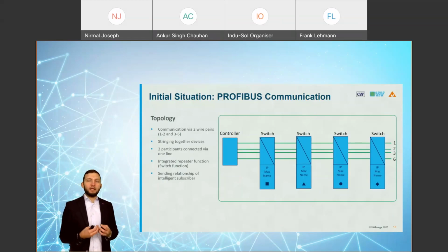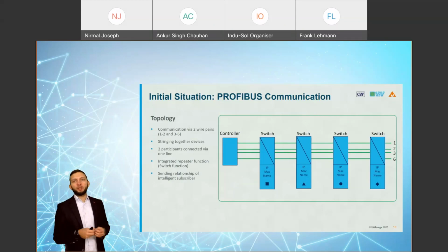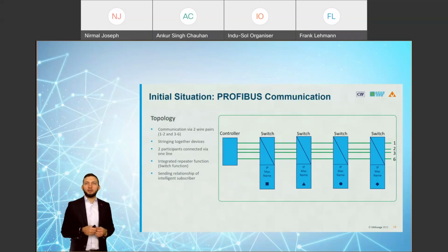Another point is that I don't have repeaters in my network, I have switches, which have higher intelligence inside than repeaters. Another benefit is that I don't have a physical line structure through all my devices; I only have a physical line structure from one device to another, so I have end-to-end communication between 2 devices. And the termination that I have to turn on in the PROFIBUS network is integrated into each device, so I don't have to turn resistors on or off in my network. This is a nice benefit, I think.